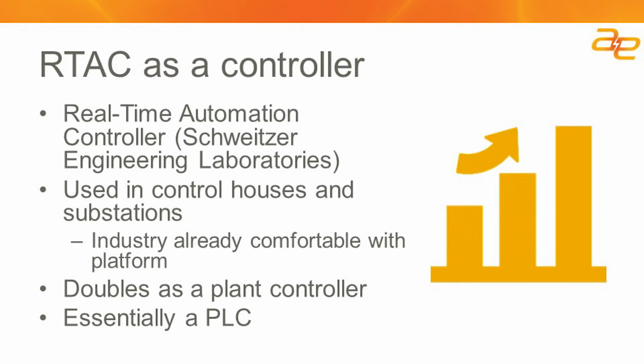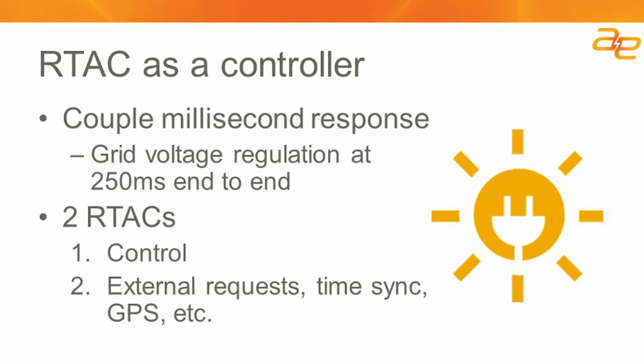As I said, we've used it successfully in several applications for qualified facilities as well as larger facilities. As far as capabilities, the RTAC is very fast response, so it's PLC-like in its response time. We can do grid voltage control at a 250 millisecond closed-loop response time. So any of the interconnection agreements that I've seen in the United States that had very specific requirements for how fast the system had to respond to a command or a change in conditions, the RTAC's capable of supporting any of those requirements.